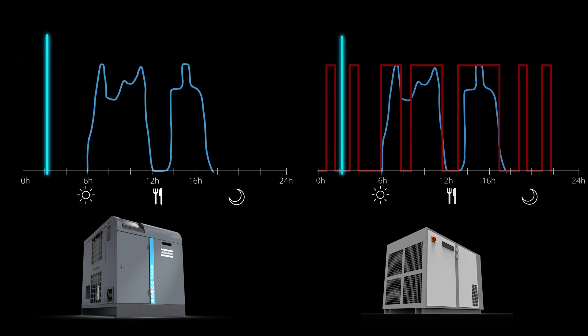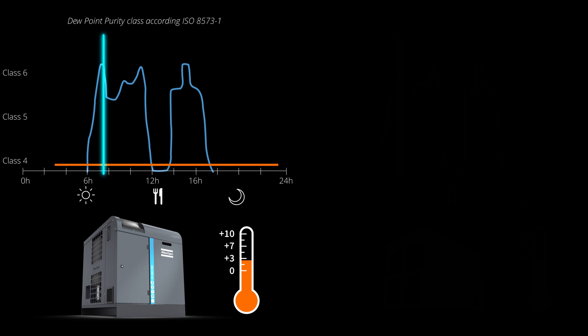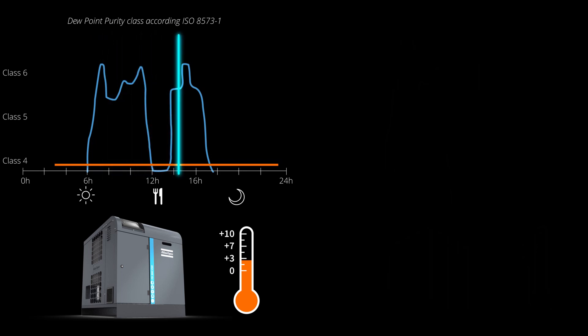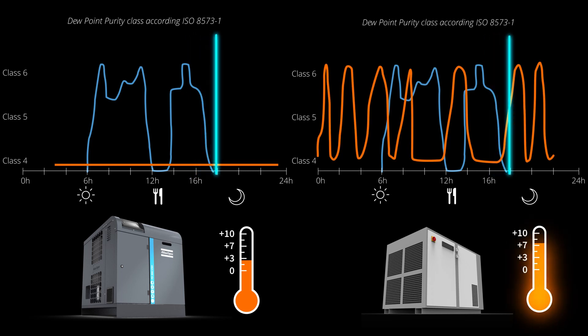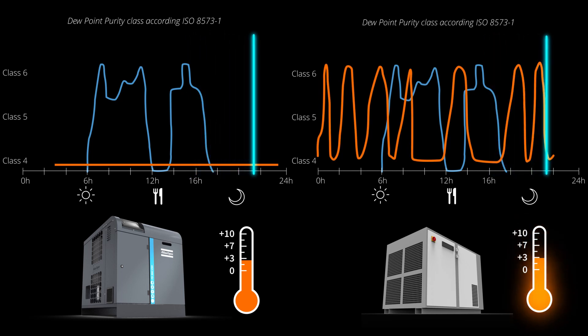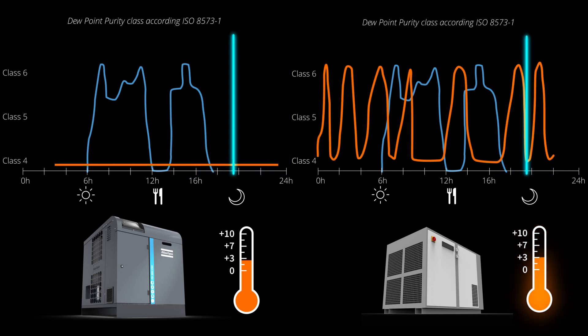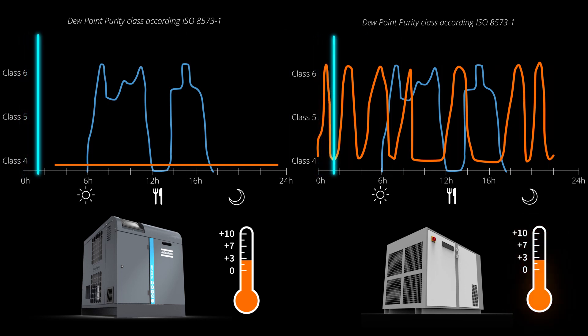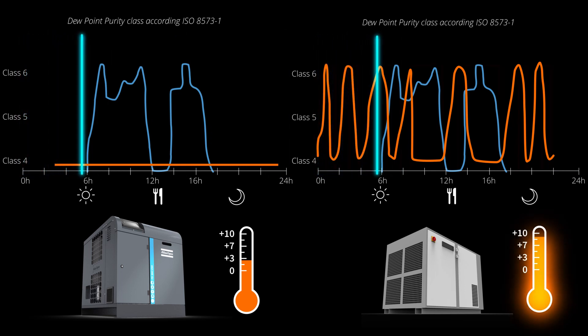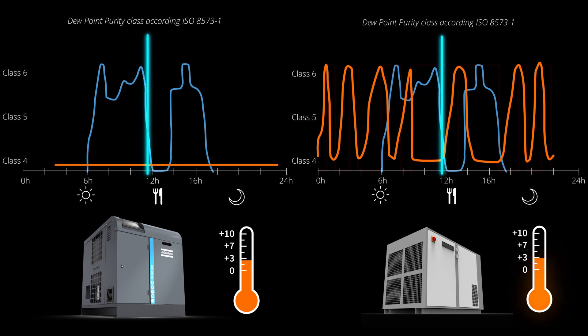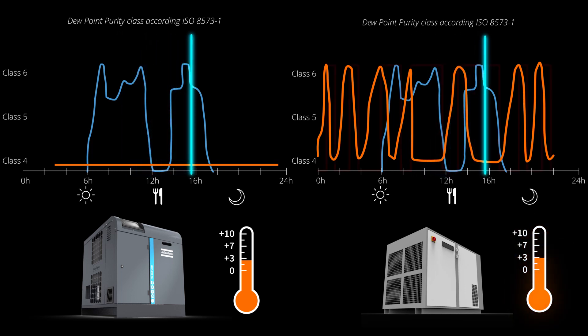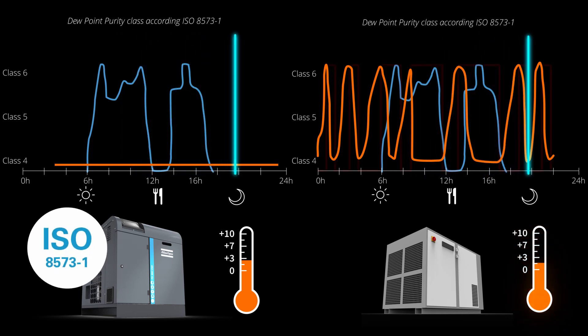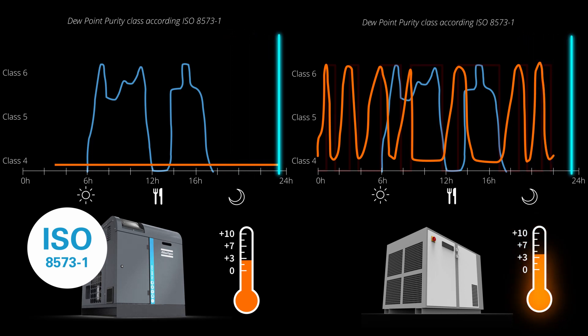Second, the FDVSD gives you a stable, low dew point and outstanding air quality. With the thermal mass dryer, your compressed air dew point rises and falls, as it is the indicator for the refrigerant compressor to start or stop. This fluctuation compromises your air quality by up to two purity classes.